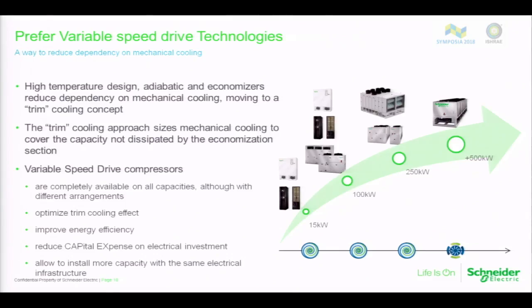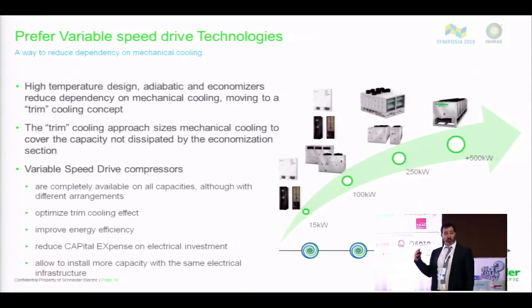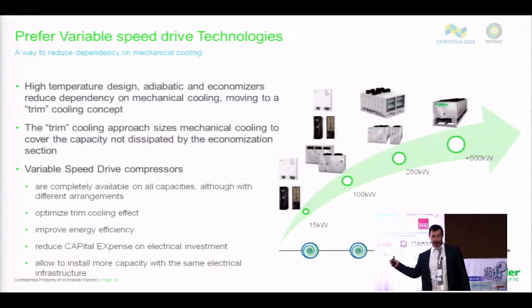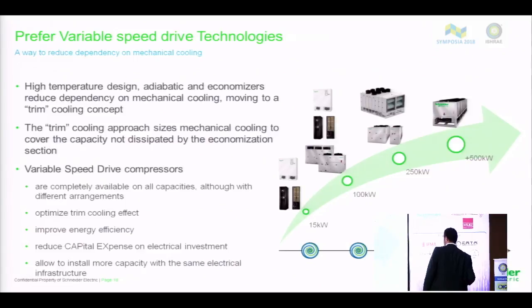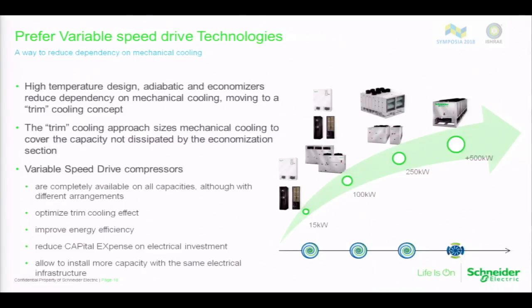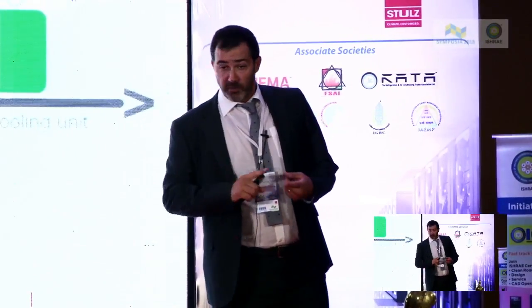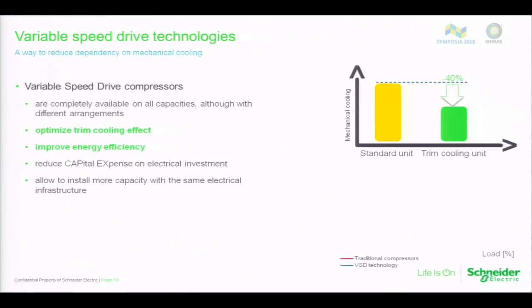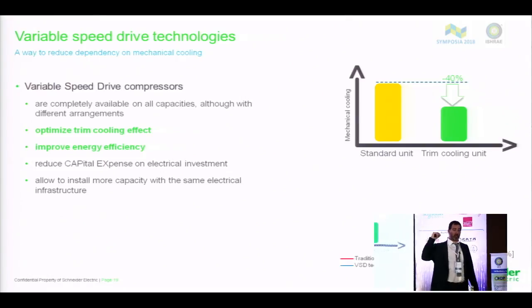We have, as many other manufacturers, a double choice, fixed and variable speed. This is not true that the variable speed are the best choice ever. It is something that we need to consider in terms of payback, in terms of approach, but it's important to have and to consider in the equation even this. Variable speed are more efficient because the compressor exactly follow the capacity, and it can be selected on the proper design.